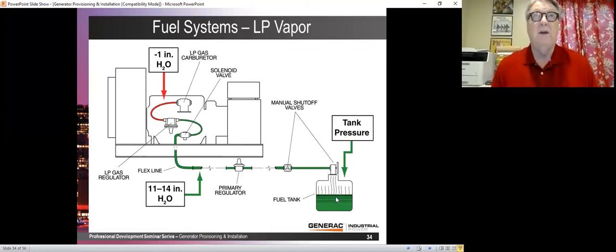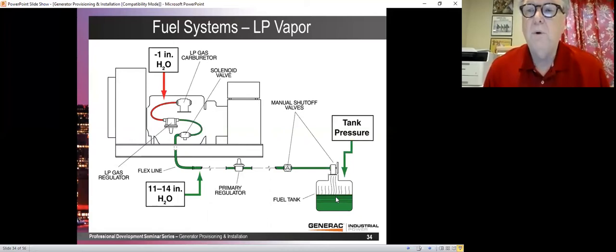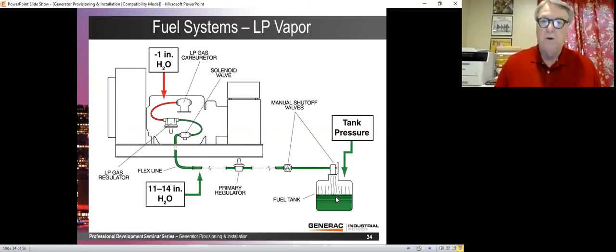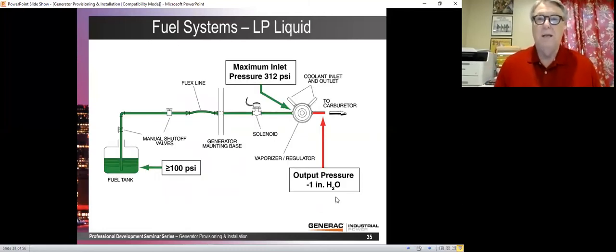a 500-gallon tank can vaporize enough fuel to run a 25 kilowatt generator. Now, a 500-gallon tank to me is kind of a big tank. It's a fairly good sized tank, and yet 25 kilowatts doesn't seem like very big. So if you have a smaller tank or you're over 25 kilowatts, the system isn't going to work well. So what you have to do then is go to a liquid-based system.